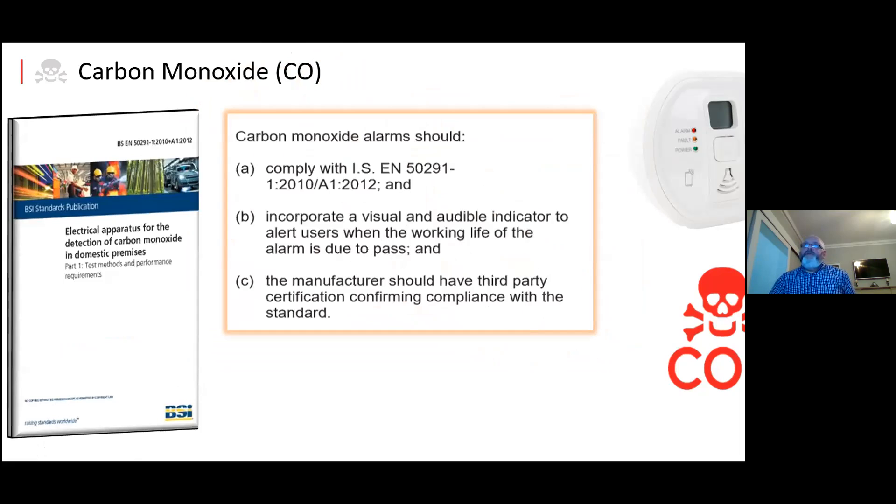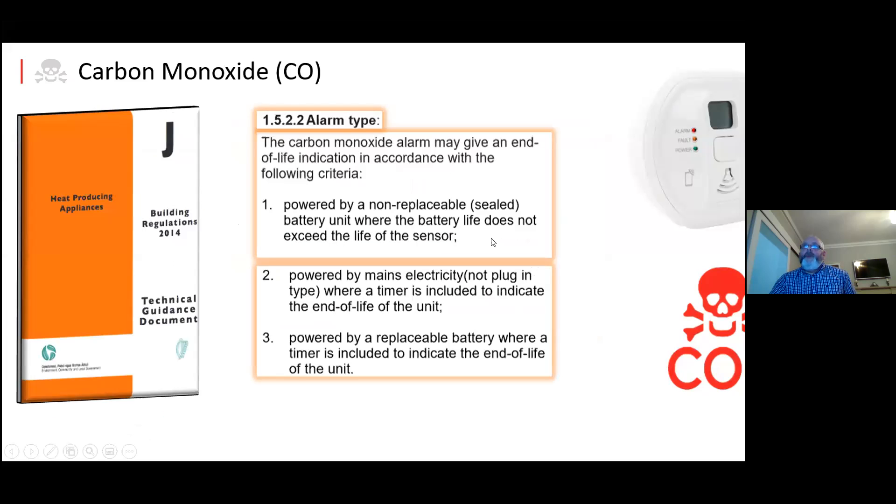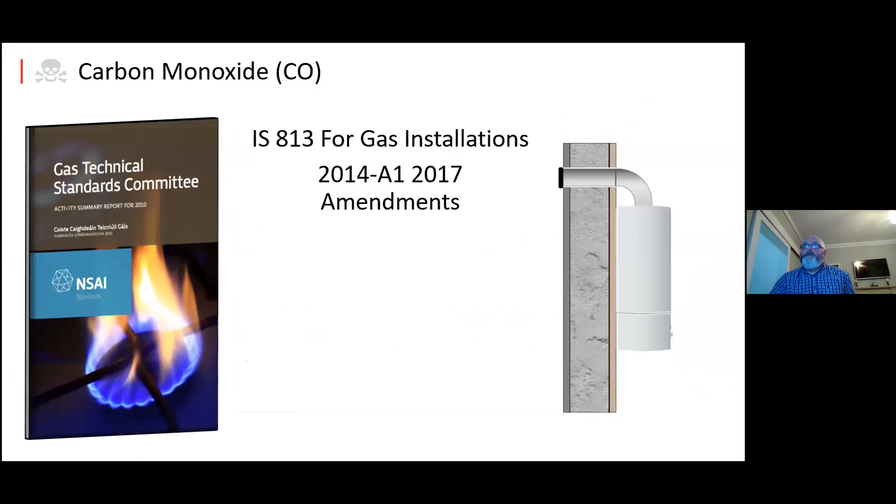The standards the device must comply with are EN 50291-1:2010 and A1:2012. It must incorporate an audible and visual indicator of end-of-life, and the manufacturer must have third-party certification. Power sources can be replaceable batteries, 10-year batteries, mains, or mains with battery backup. The only unit that's not allowed is a plug-in type.